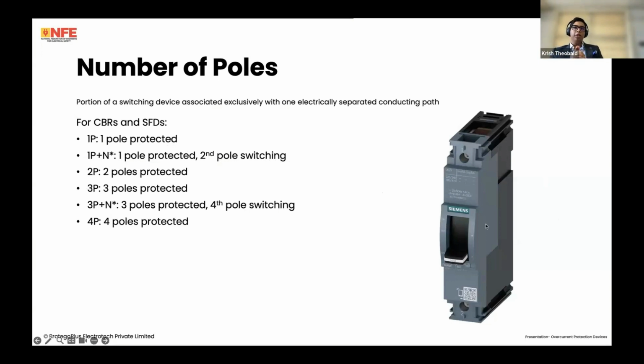Then you have your one pole plus neutral. This is a very commonly used term. What it means is that one pole is protected and the second pole is switching. However, if it is a switch fuse disconnector, one pole plus neutral often means that the two poles are going to be having a fuse holder, and the one may either be a switched or an unswitched link.